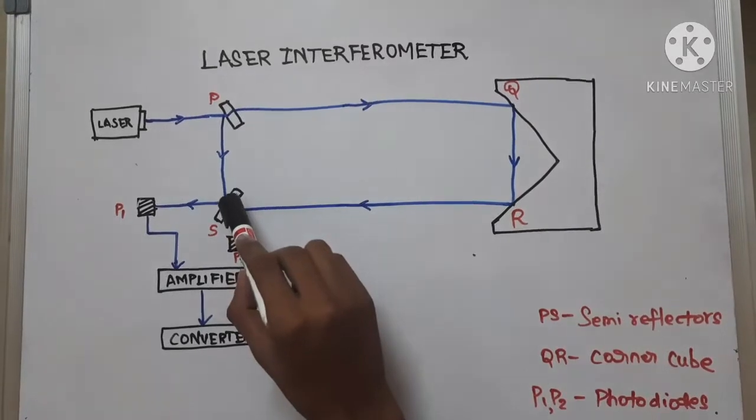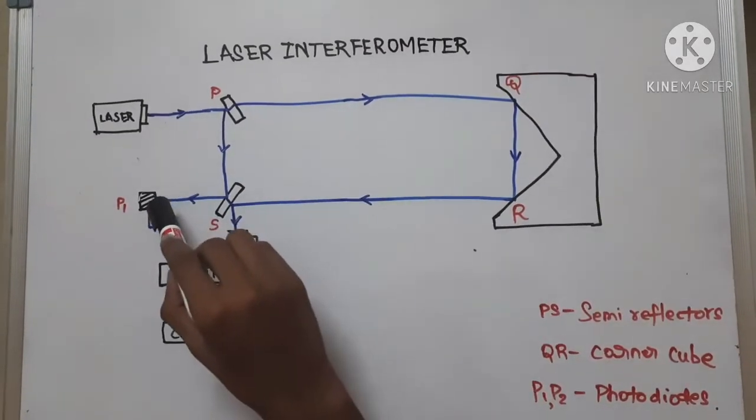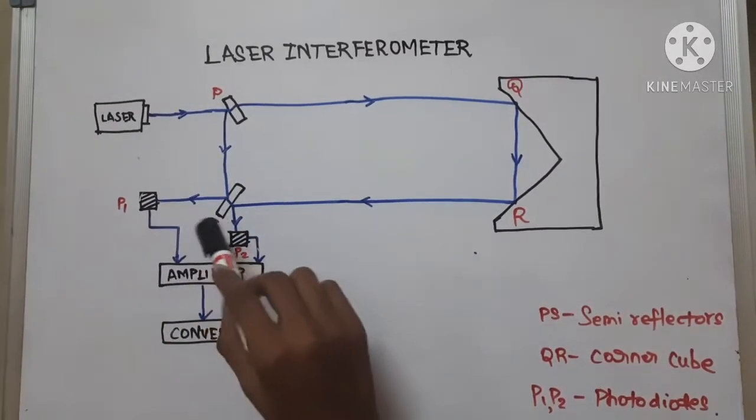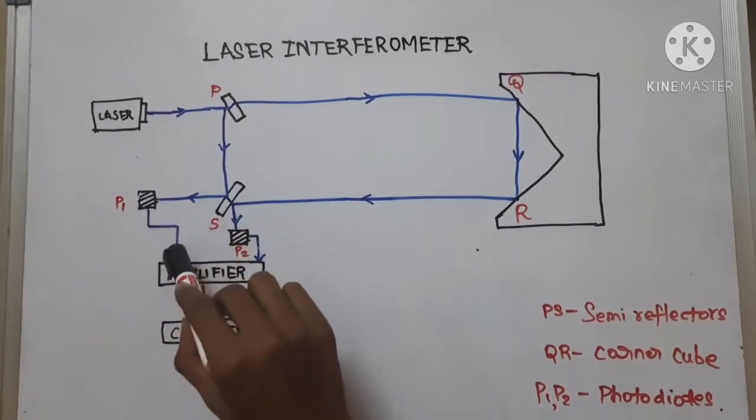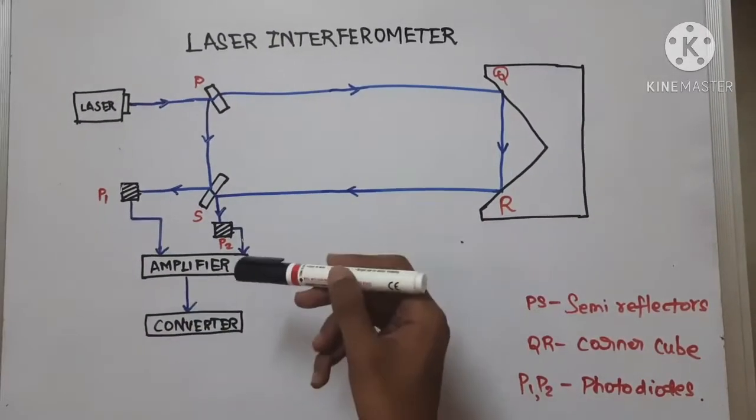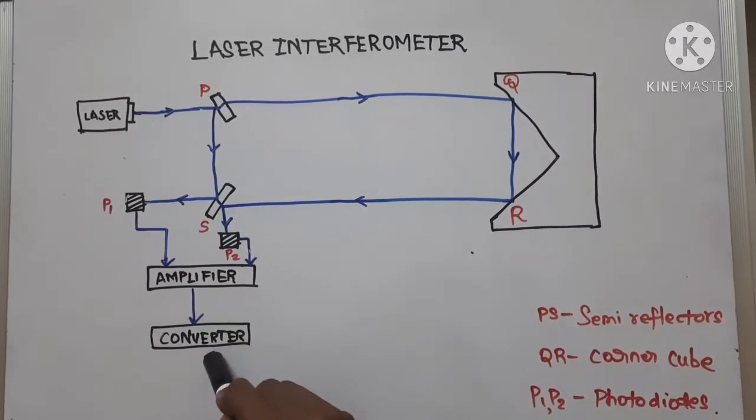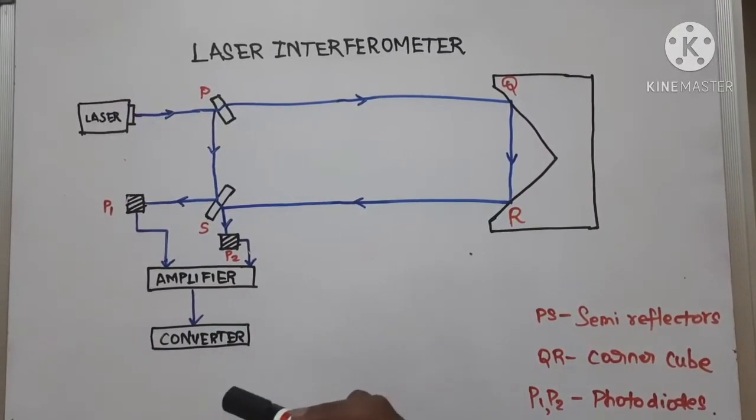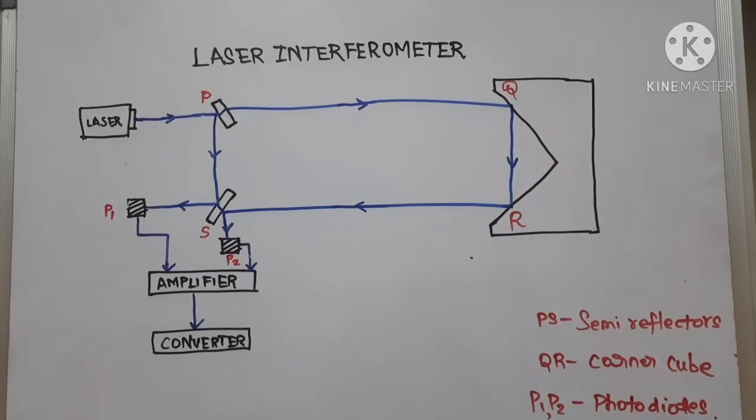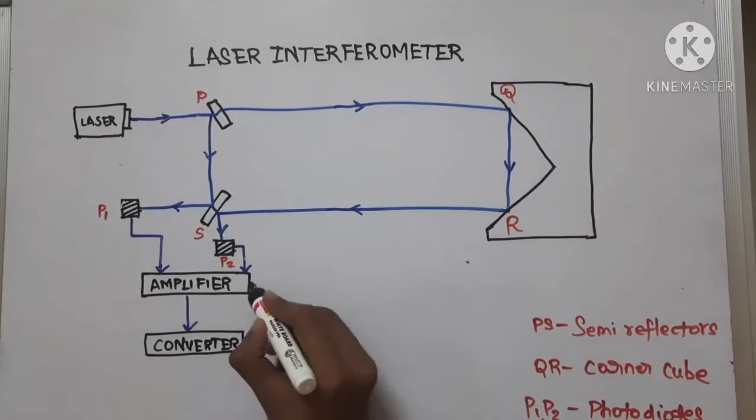And a part of light again passes through this plate and hits the photodiode P1. So these two photodiodes are connected to the amplifier which amplifies the signal and that signal gets received by the converter which measures the fringes. And the amplifier gives this to an output.